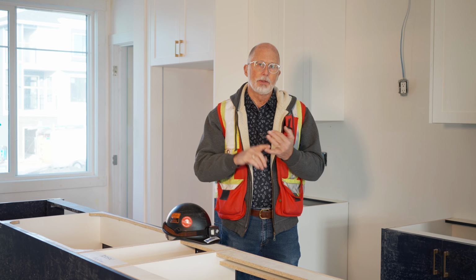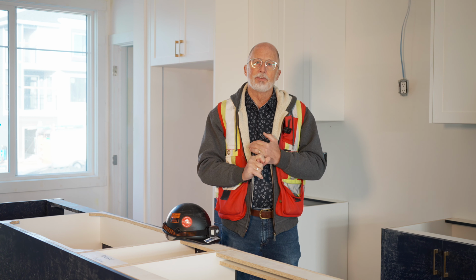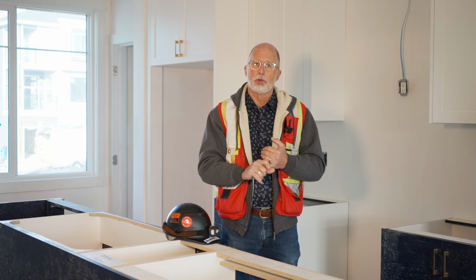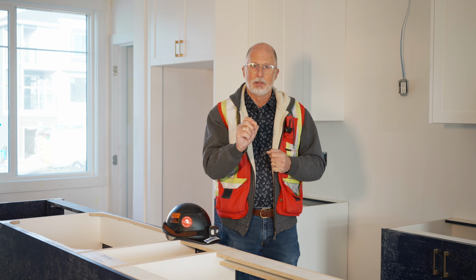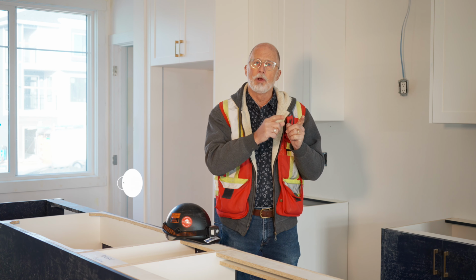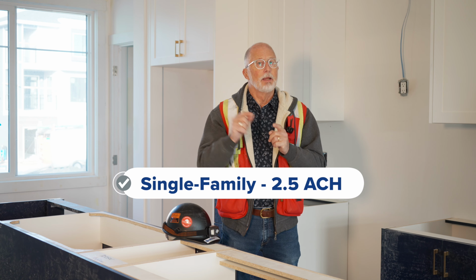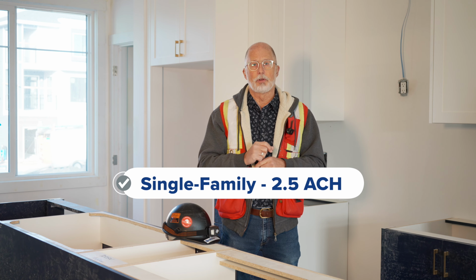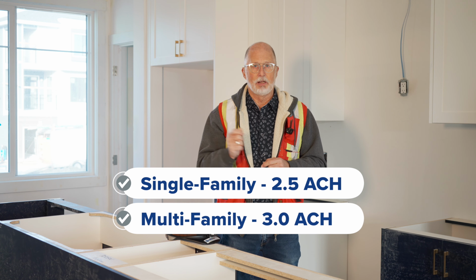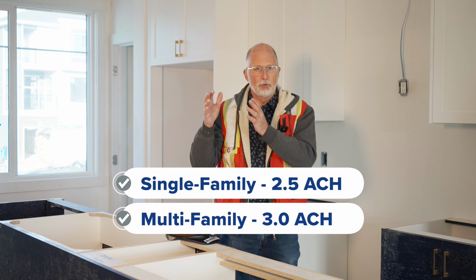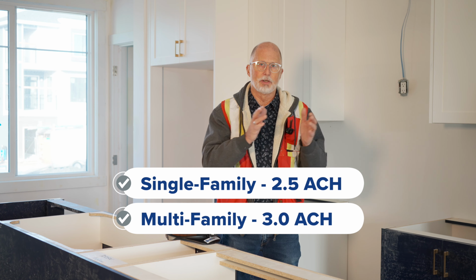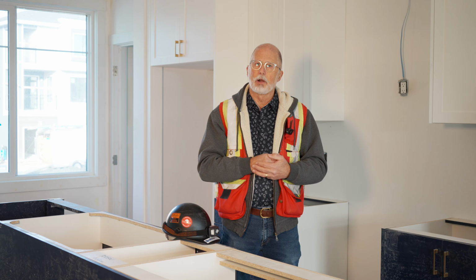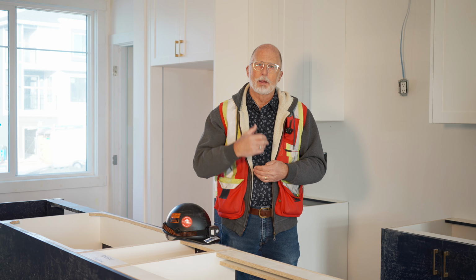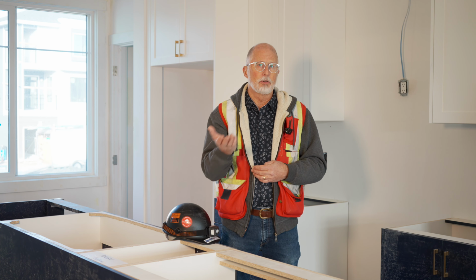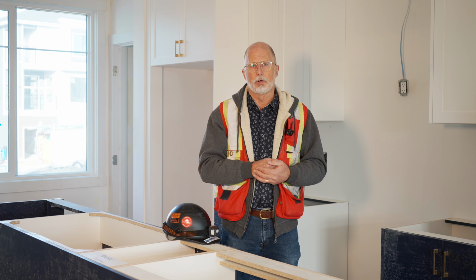So in the building code, what they've done is they've addressed that by saying your reference house in single family needs to be 2.5 ACH. In multifamily, they now allow us to be 3 ACH for multifamily when we have those connected zones between each other. So that's going to help us with our energy efficiency because our comparative is 3 instead of 2.5 like it was in the previous code.